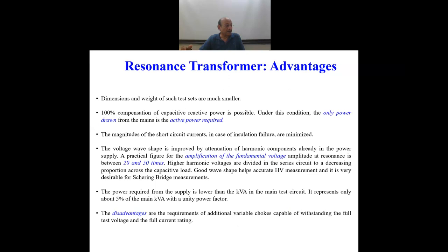Then the voltage wave shape is improved. When the reactive current is not being drawn, the voltage wave shape of the power frequency, because it is now applied only to the resistive load, improves by attenuation of harmonic components already in the power supply. The voltage wave shape is improved. Then the practical figure of the amplification of the fundamental voltage amplitude at resonance is between 20 and 50 times. It is reduced.